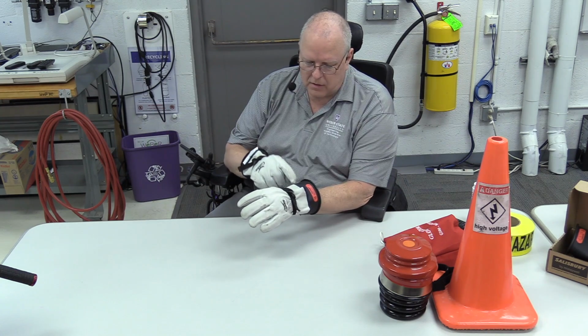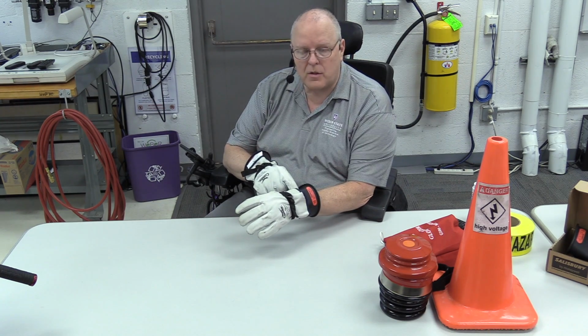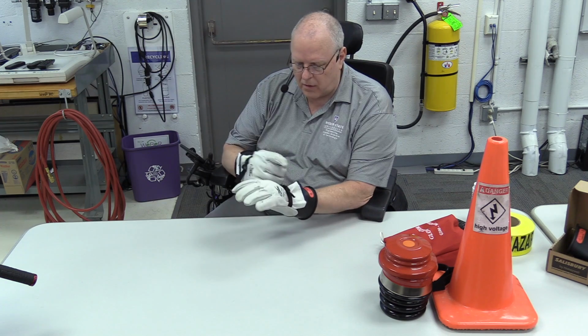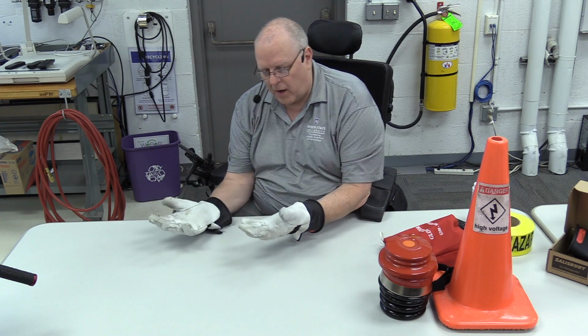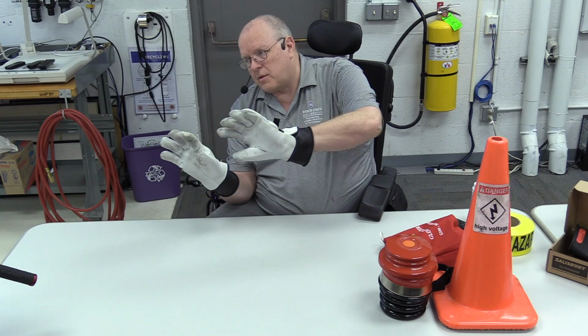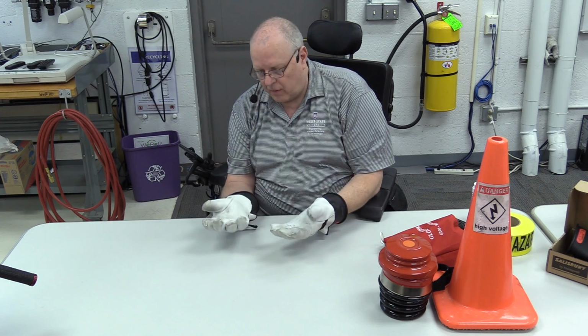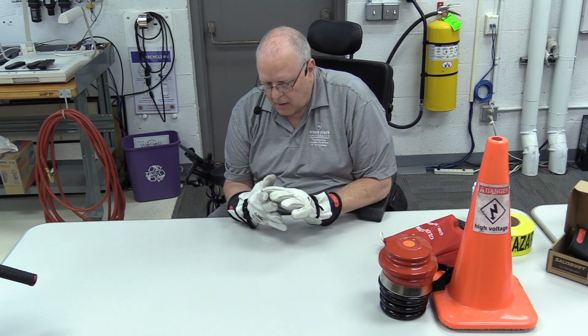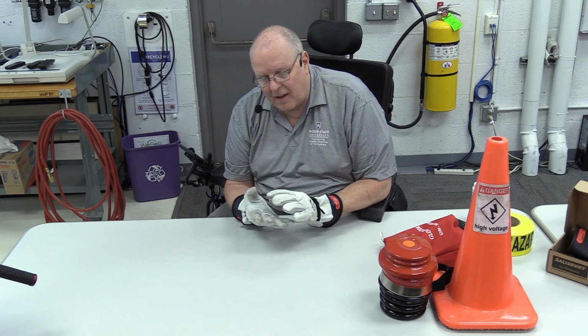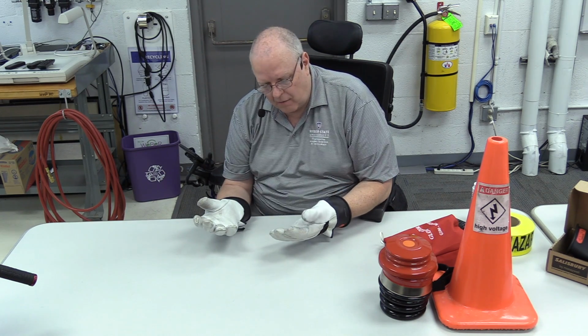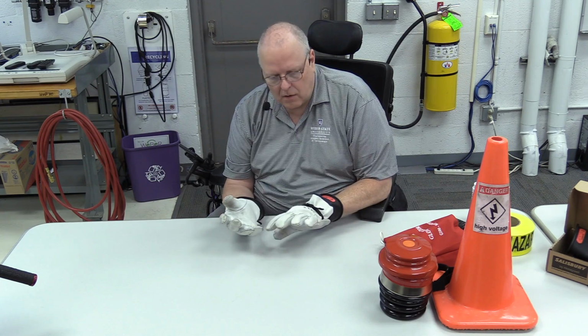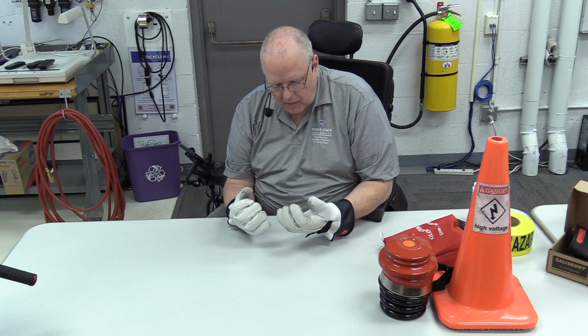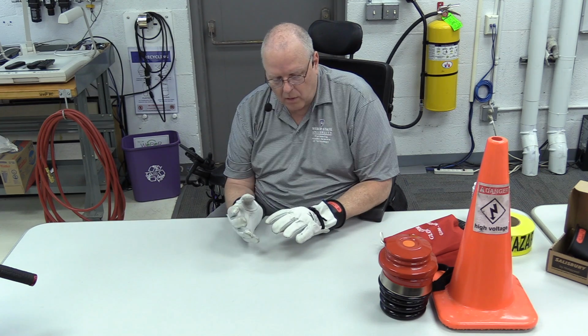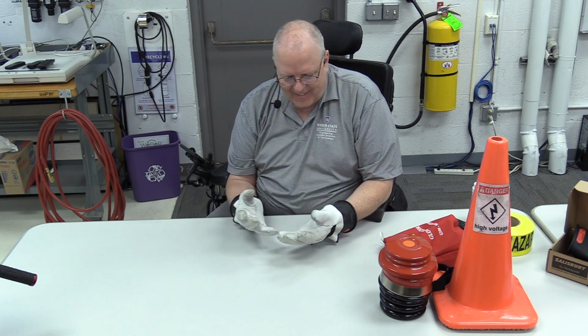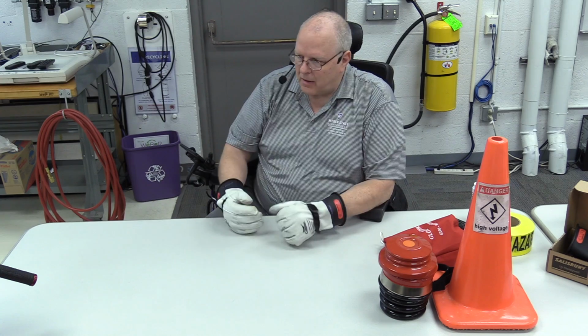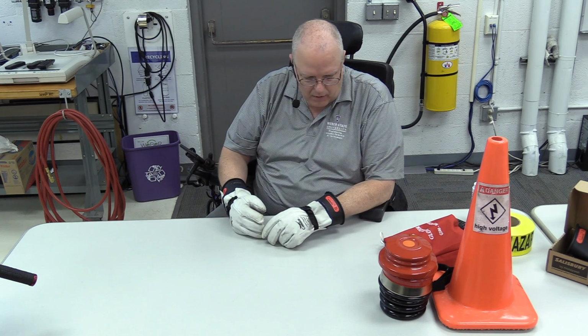But now I have on some tested gloves for leaks. They're within the certification range as far as the law and the standards are concerned. And I have some leather outer gloves. These leather outer gloves are dirty because we've used them in class many times. Just don't forget that as they get dirty, they become conductive, so these really need to be cleaned periodically to prevent the outer glove itself from being the conductor that you're trying to avoid.